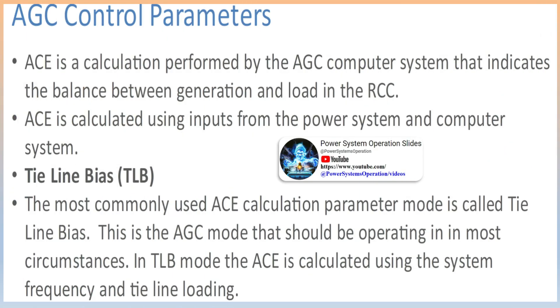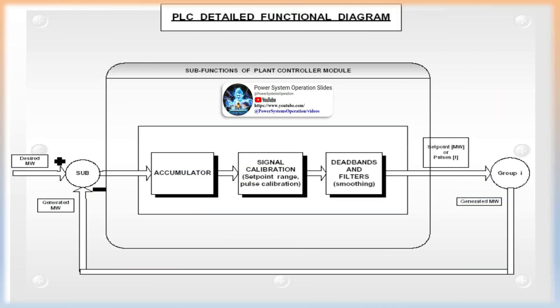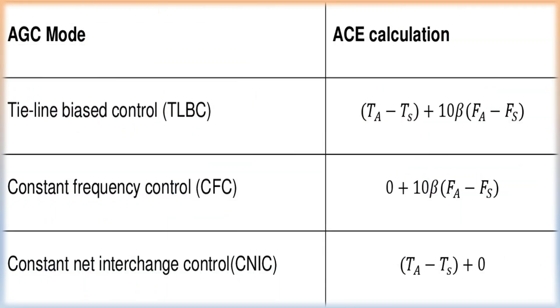Switching AGC to constant net interchange control would only be done if all frequency signals were lost. The ACE calculation equation for CNIC is: ACE = MW flow minus MW target. Constant frequency control CFC: a third AGC mode available to the generation dispatcher is constant frequency control. In this mode, the interchange or flow component of the ACE calculation is removed. The AGC will only respond to frequency change to satisfy the frequency target, and will pulse the generation to ensure frequency is maintained. The only time CFC should be used is if the operating area is isolated and operating as an island. Caution must be taken to ensure the bias setting is adjusted properly for isolated operation or frequency can deviate considerably.